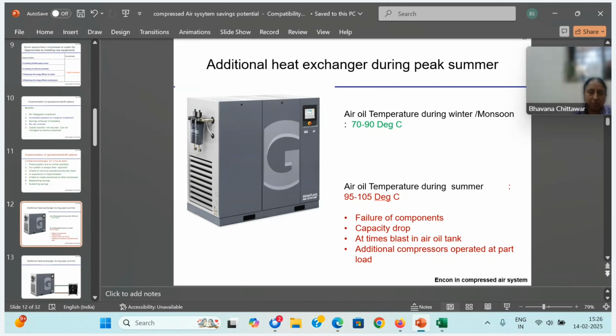The screw compressor packages that we get, most of the screw compressors, are all designed for low ambient conditions, not for tropical countries like India. Even if you take Atlas Copco or Kaeser or whoever it may be, they have all designed their equipment for their own 20-degree ambient. If you check their certificate or check the quotation properly, the parameters will be only for 20 degrees. Whereas our ambient is slowly going up to 40 and above. Last year, a place like Bhadrachalam in Andhra Pradesh recorded 48 and above. It has touched 50 degrees. At 50 degrees, these equipments will not run. I expect another 2 or 3 degrees this year also. Then all these equipments will run into problems.